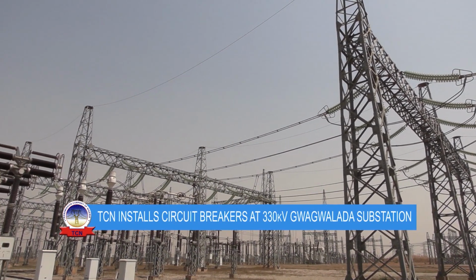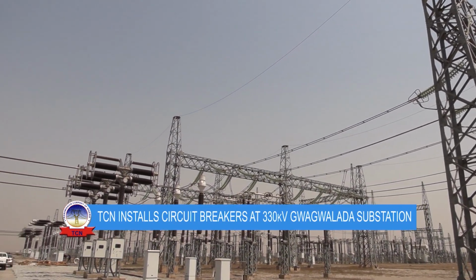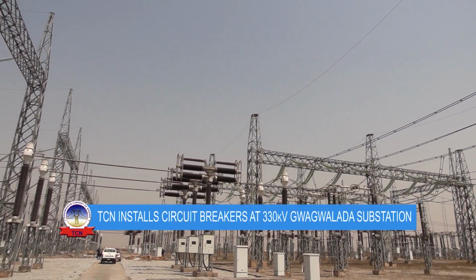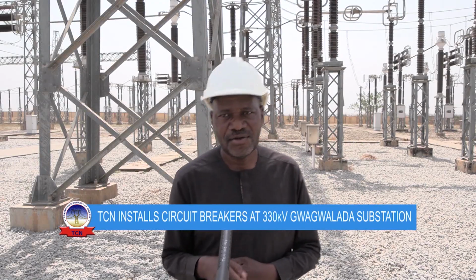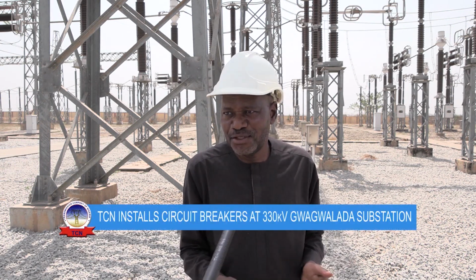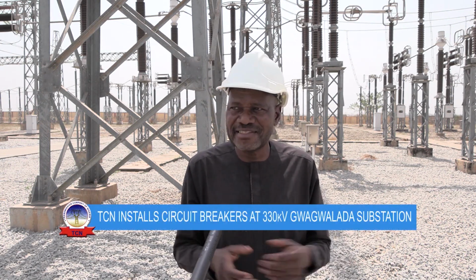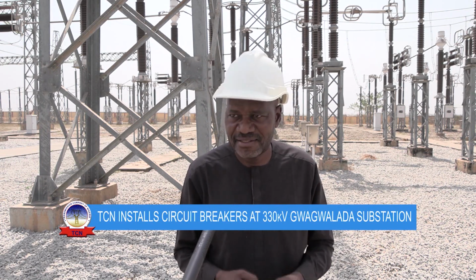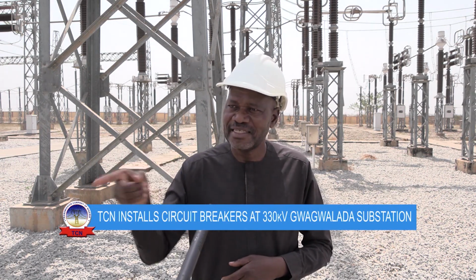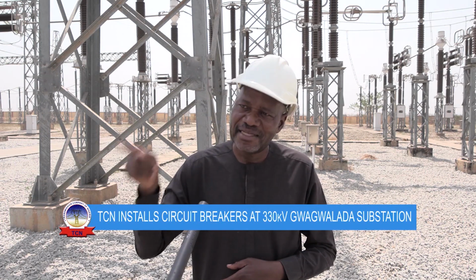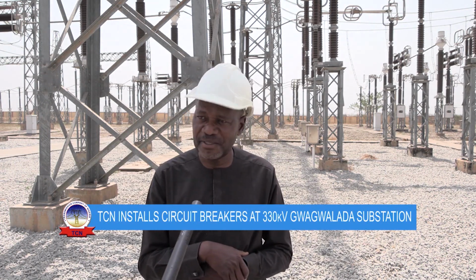Transmission has provided for this in the event of any disturbance, because this transmission network now operates under N-1. If you lose one element of your network, the remaining network under N-1 will still be able to cater for what is expected. So for us to make sure the system is solidly linked, we are replacing this breaker that has run short of spare parts.